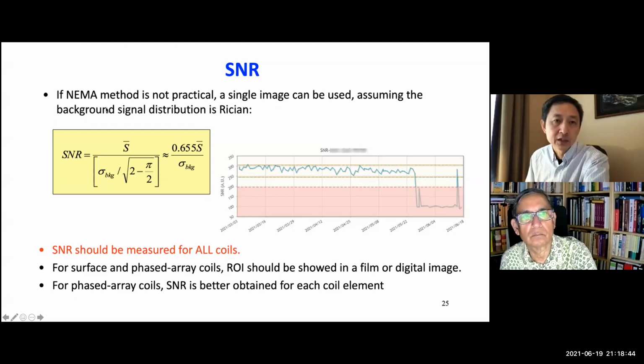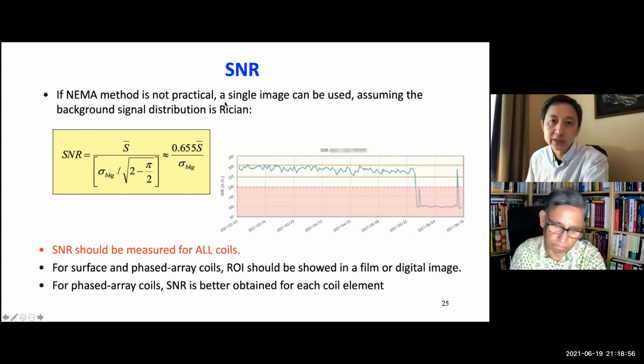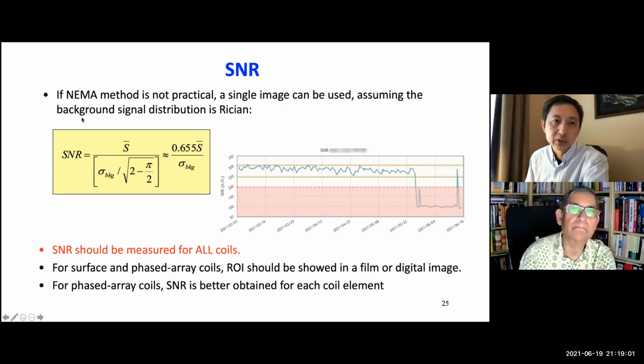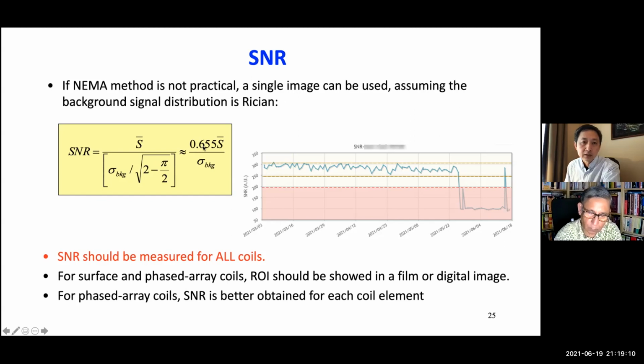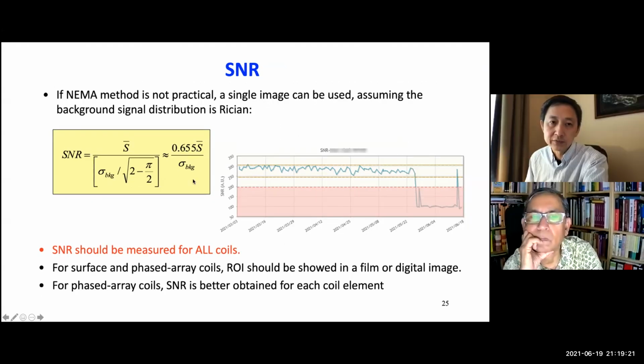However, in many situations, NEMA is not practical because we need to make two measurements each time. There are so many coils. So there are other methods developed. The simplest method is just to look at a single image, and then we assume the background signal, when there's no signal, the distribution should be a Rician distribution. And with a Rician distribution, the SNR is calculated by the average signal within the phantom divided by the standard deviation outside of the phantom, the background, multiplied by 0.655.